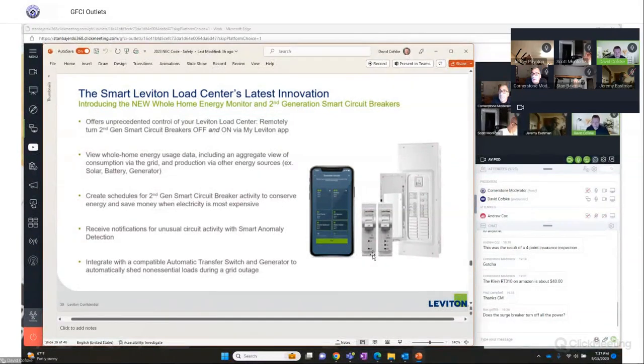Hey, Dave. Yeah. On the surge breakers, does that turn off power to the whole panel? On the master surge? So on the surge breaker, it won't turn off power in the panel. The surge breaker will take a hit. When the surge breaker is no longer protecting your panel, it has an LED on it as well, and it will tell you that it's at the end of life.